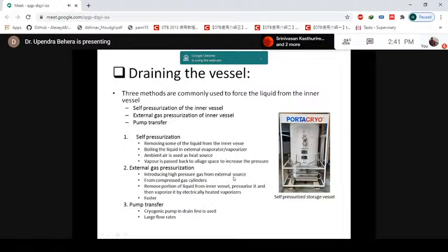By external gas pressurization, as the name indicates, you pressurize the container by an external source. Maybe you can use compressed gas cylinders, whatever gas is there. You can use nitrogen, generally pressurized by nitrogen gas, because helium is very costly compared to nitrogen, which is plentifully available. The other method is to remove a portion of the liquid from the inner vessel, pressurize it with some machine or compressor, then vaporize it by electrically heated vaporizers. That way it is faster compared to self pressurization, but additional equipment is needed, like either a gas cylinder or a compression system for pressurizing the liquid, taking it to vaporize and filling it again for pressure building.